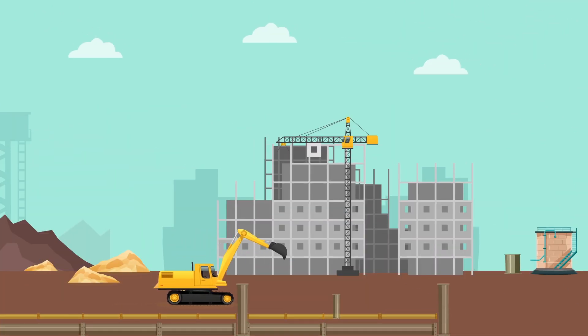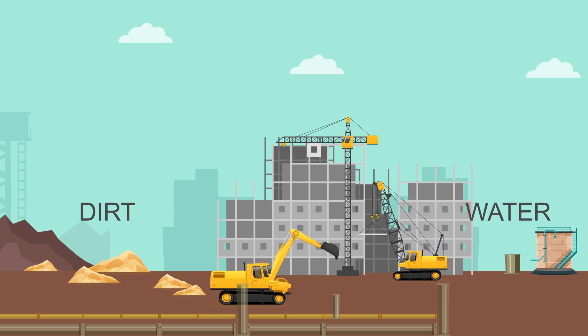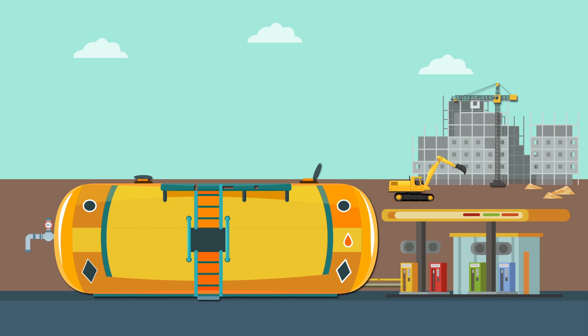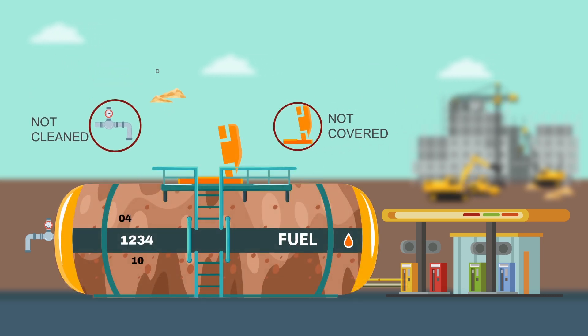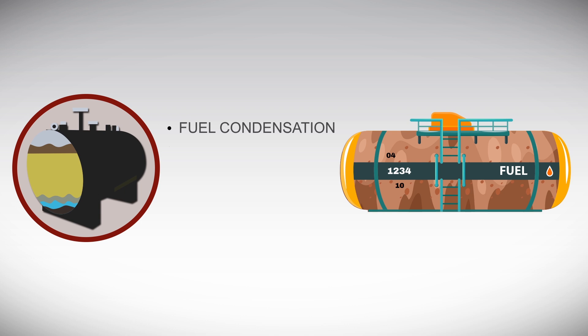There are many sources of dirt and water at the site, which often includes rust and corrosion residue in pipelines, which in turn may lead to leakages. It is critical that fuel quality is maintained at the right levels at the bulk tanks. If fuel tanks are not cleaned and covered properly, this may allow dirt and water to enter the storage tanks.